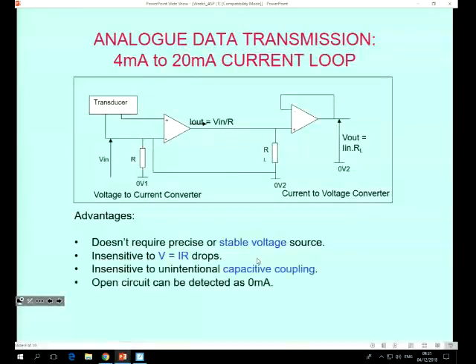Capacitive coupling we talked about, open circuit being detected as 0 milliamps. Oh yeah, another good point is you can have these at different earths. Because you're sending current, you don't have to have a reference voltage to be able to measure a different voltage from - you just measure the current. You need a reference current, but your reference current is probably 0 milliamps, so that's fine. This was quite useful when we used to test the radar, because we used to float the high voltage side of it at a higher voltage earth point.